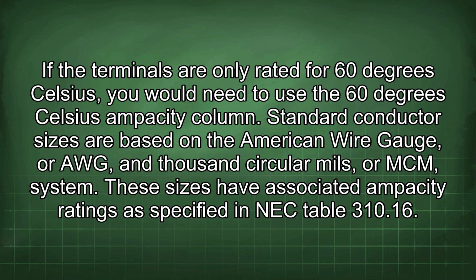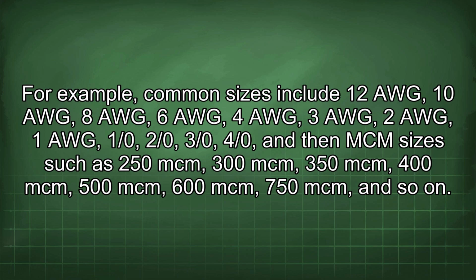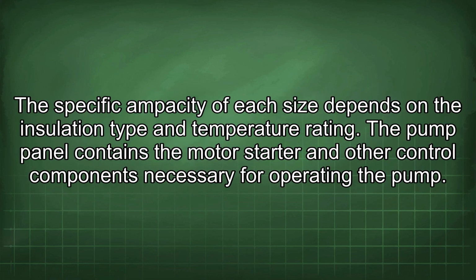Standard conductor sizes are based on the American wire gauge, or AWG, and 1000 circular mils, or MCM system. These sizes have associated ampacity ratings as specified in NEC Table 310.16. For example, common sizes include 12 AWG, 10 AWG, 8 AWG, 6 AWG, 4 AWG, 3 AWG, 2 AWG, 1 AWG, 1/0, 2/0, 3/0, 4/0, and then MCM sizes such as 250 MCM, 300 MCM, 350 MCM, 400 MCM, 500 MCM, 600 MCM, 750 MCM, and so on. The specific ampacity of each size depends on the insulation type and temperature rating.